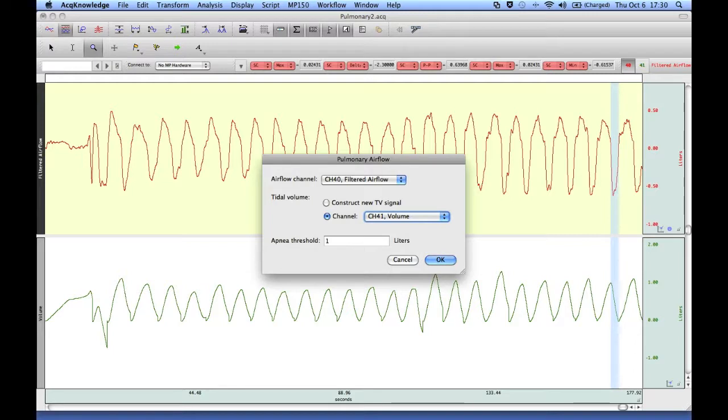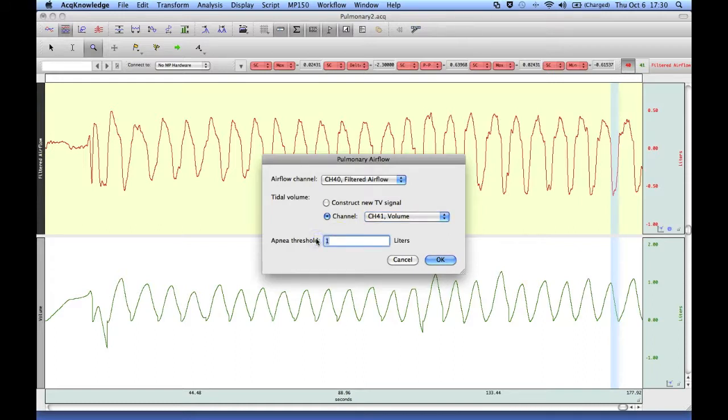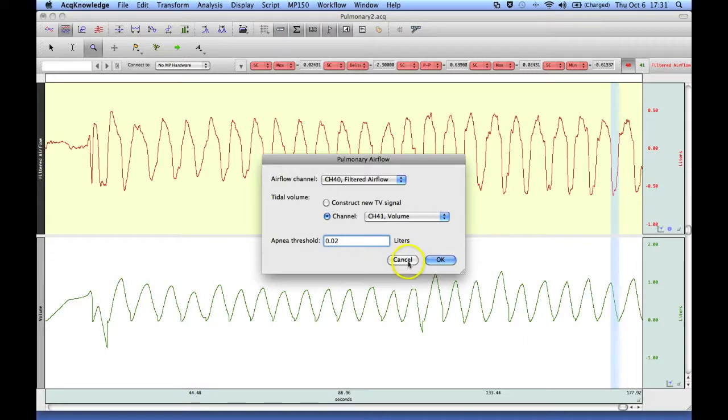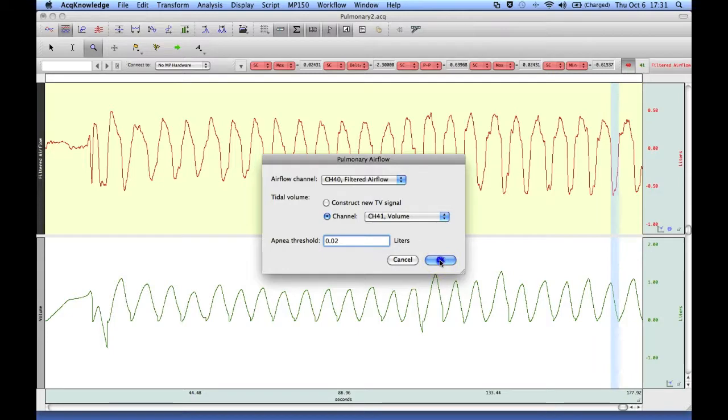And as the signal crosses through on the negative side, it will mark that as the expiration. What I'm going to do is set that slightly above zero, just in case there's a little bit of noise in the signal, and we'll see how we do with this level. And we can play around with this if needs be.